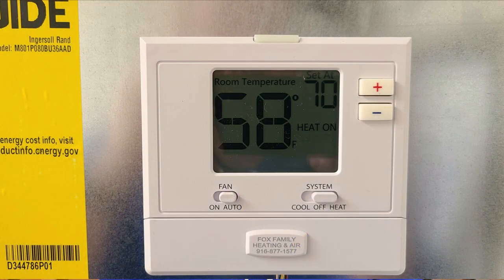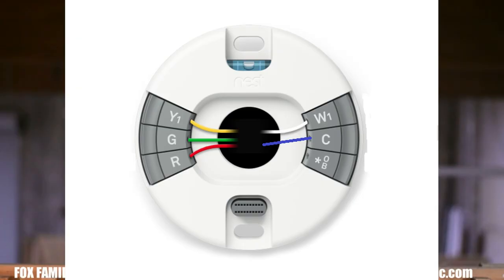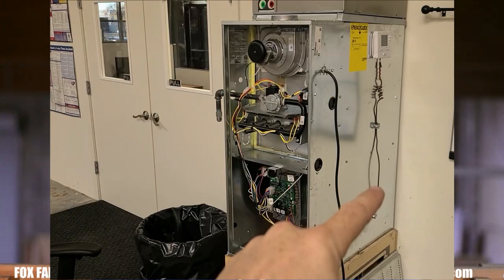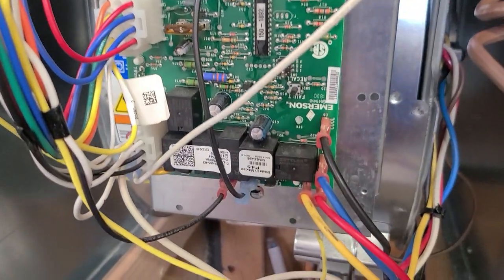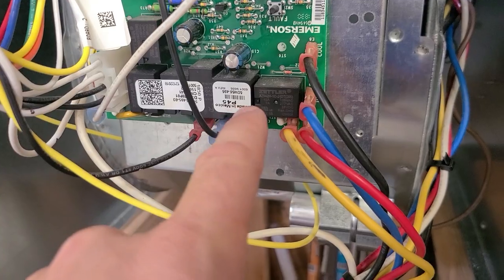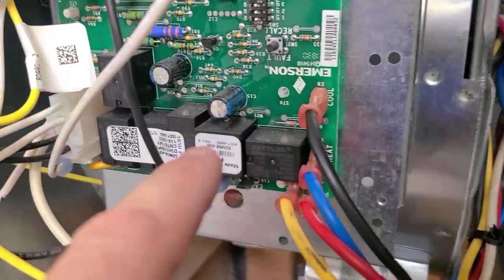When your house reaches a point where the heat needs to come on to keep you comfortable, a series of components work in a certain order to produce that heat. The thermostat is the first part in that sequence. There is 24V power at the R terminal of the thermostat already. Within the workings of the thermostat, 24V closes a switch at the W terminal, and that signal is sent to the control board back at the furnace. The control board is a printed circuit board that has various switches, resistors, and terminals that act as the quarterback of the heating system.